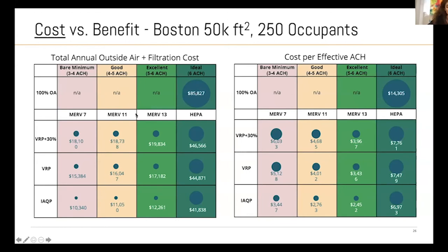You can definitely do it. But you can actually achieve an excellent air exchange rate, 5 to 6, but way less costly than basically 85,000. It only costs you this much. Again, this is specific to the rates and the climate in Boston. There's also a way to calculate cost per effective air exchange rate. This is a metric I was talking about at the beginning, dollar per risk reduction or dollar per air exchange rate.